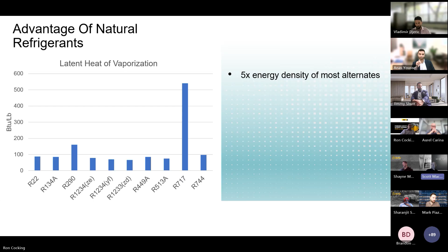Ammonia has 5 times the energy density of most alternate refrigerants available to us. What that means is basically it has more latent heat of vaporization. It can do more cooling work per pound of refrigerant. So when we look at this chart, we can see R717 ammonia compared to many alternates we would see out there, and it's head and shoulders above in its ability to perform. Next slide.